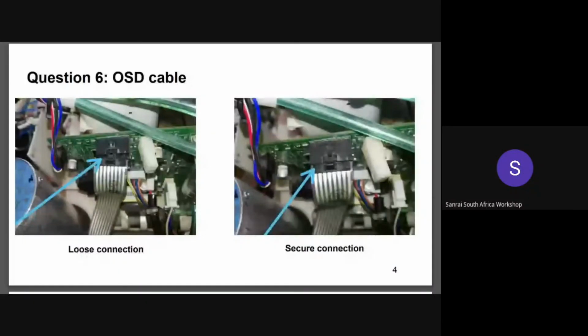With the light emitting diodes not illuminating, firstly check the connection on the PC board, since there might be a loose connection with the OSD cable. If there are any loose connections, please secure the connection and the LED will illuminate. If the situation does not change, the problem might be with the PC board, so you are advised to change the PC board.